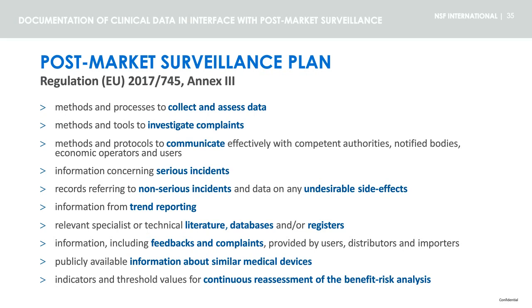For that, a post-market surveillance plan should be prepared and include important aspects such as how the data will be collected and assessed, investigation of complaints, protocol for communication, recording of serious and non-serious incidents, information from trend reporting, searches in the literature, databases and registers, including similar devices, and a continuous reassessment of the benefit-risk analysis.